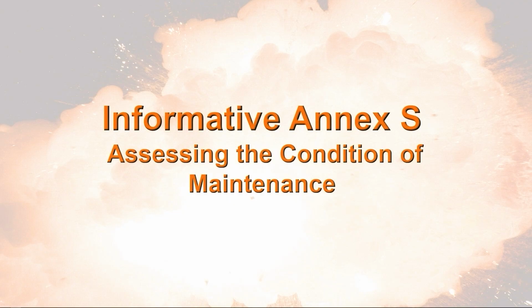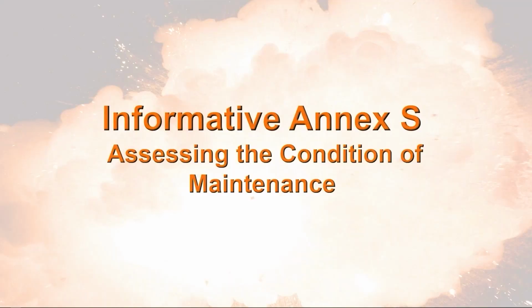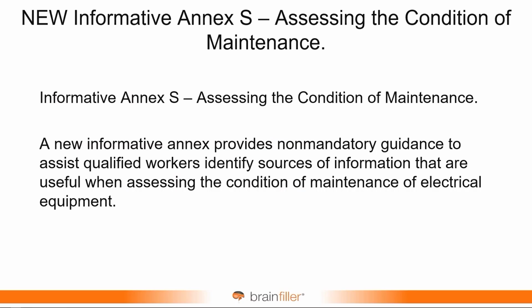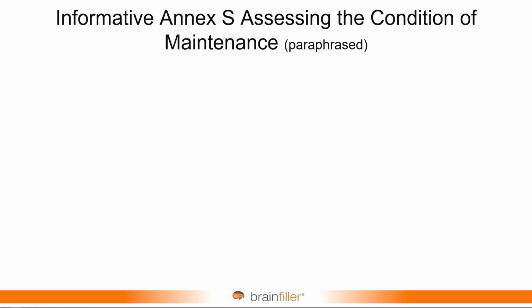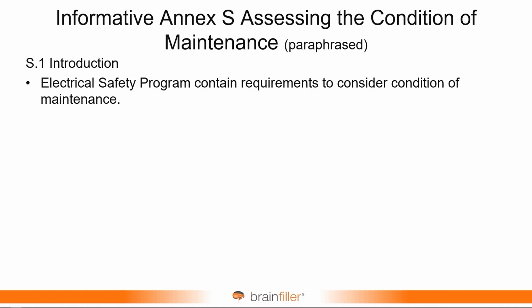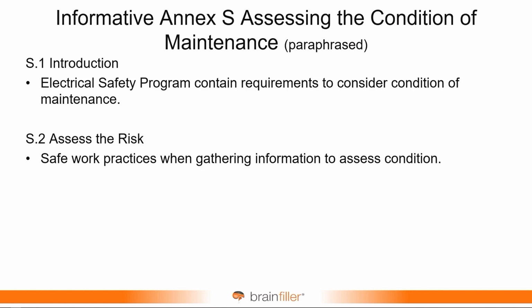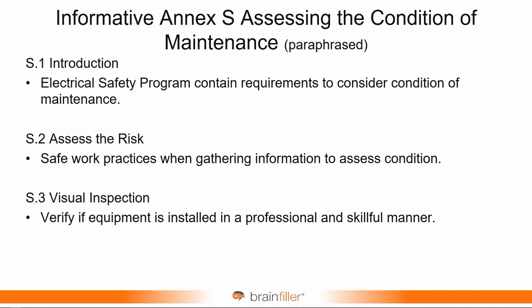There's a new annex, Informative Annex S, assessing the condition of maintenance. You see the term condition of maintenance used a number of times through NFPA 70E. The equipment shall be properly maintained. You assess the condition of maintenance. Well, how do you do that? So Annex S was added to give guidance for assessing the condition of maintenance. Annex S is made of many items. S.1 is the introduction. S.2 is assessing the risk. S.3 is providing a visual inspection.